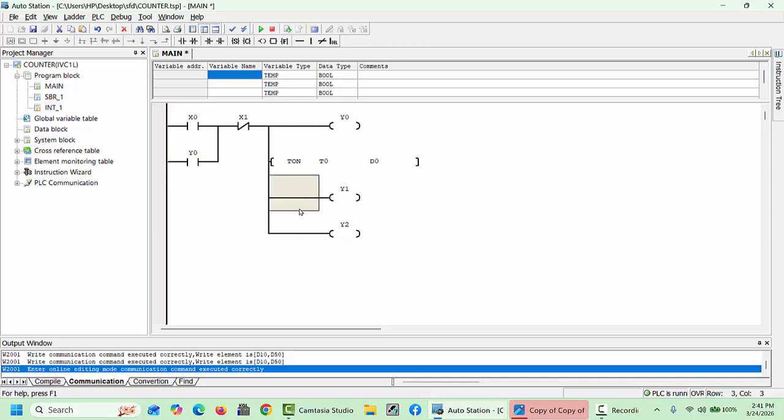So here we will take this, and these contacts need to continue to start, meaning when our main motor and main contactor have started, our star contactor must be on, and we only have to make the timing between this y1 and y2. y1 will stop and y2 will start. So here we will use the close contact of the timer t0.